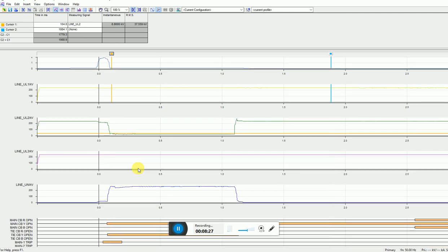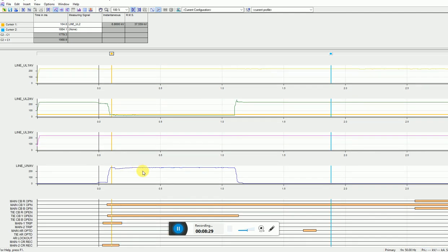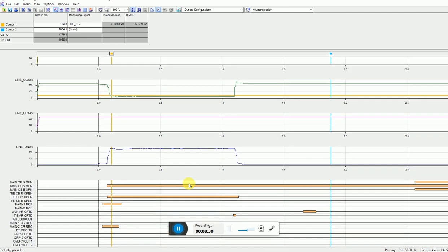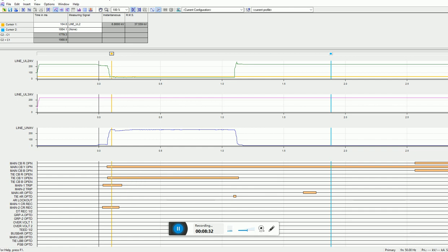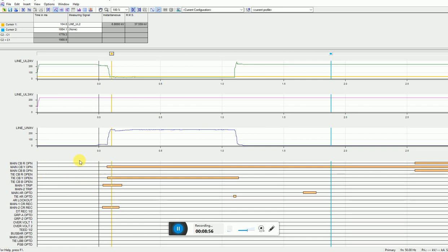Let us see the digital channel, what happened. You can see here, there is a fault in Y phase. So my relay detected the fault and it will immediately trip the Y phase breaker. Here Y phase breaker got opened immediately. Both main and tie breaker got opened immediately due to fault. Here you can see this digital channel got highlighted. Before that is normal, there is nothing happened. When there is a fault on Y phase, suddenly this main and tie breaker open. This is the trip relay, main trip relay, due to fault relay got tripped.